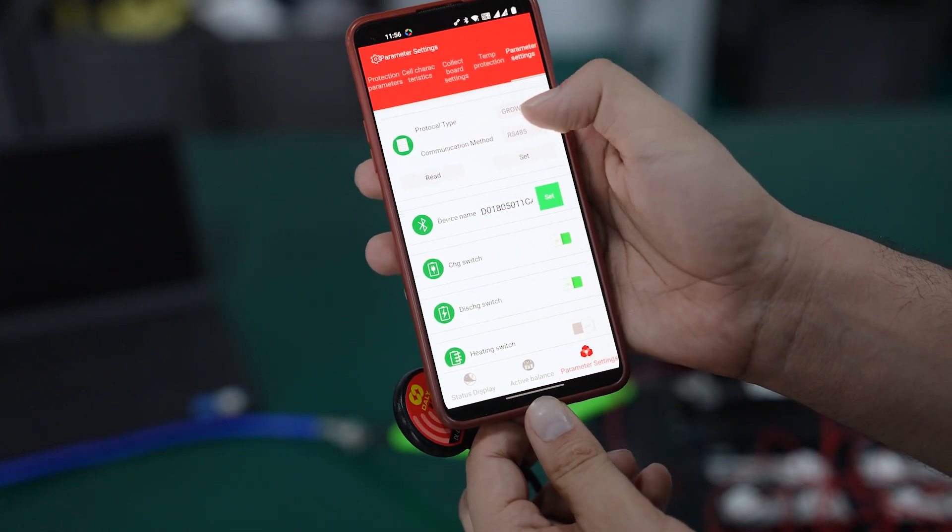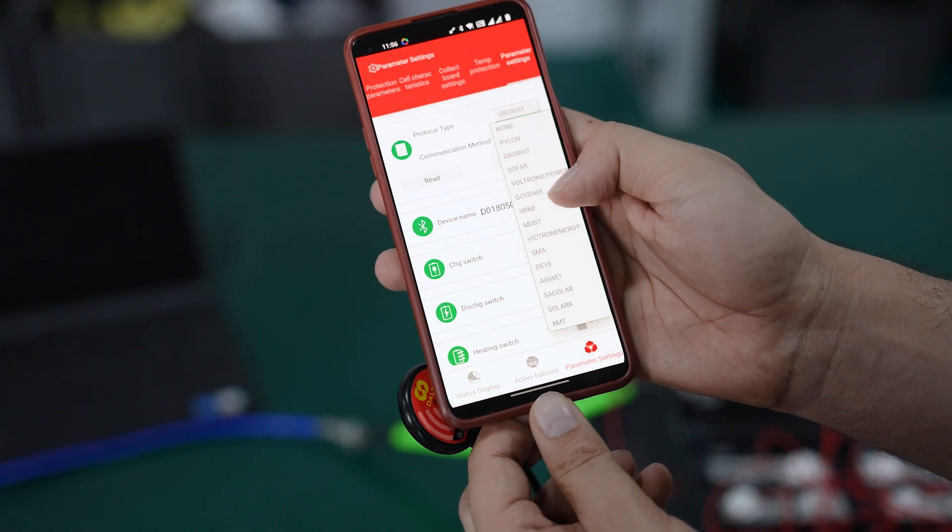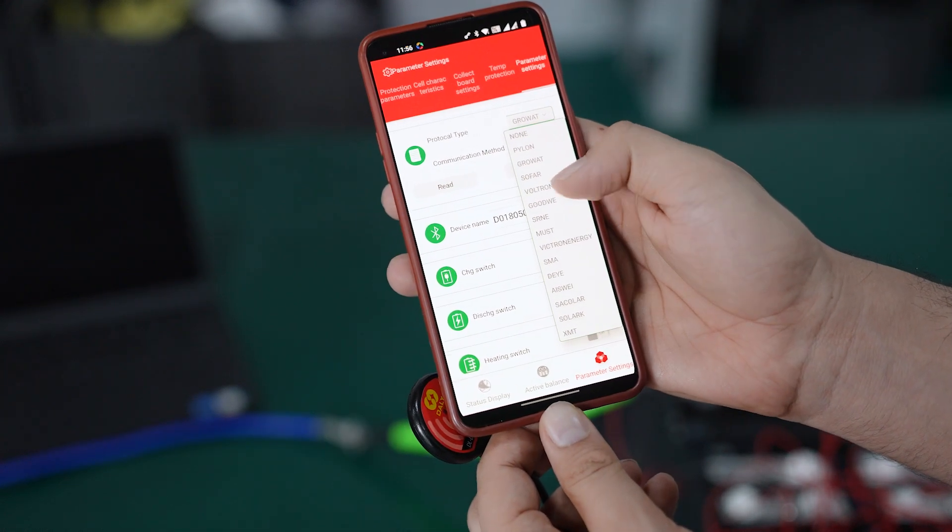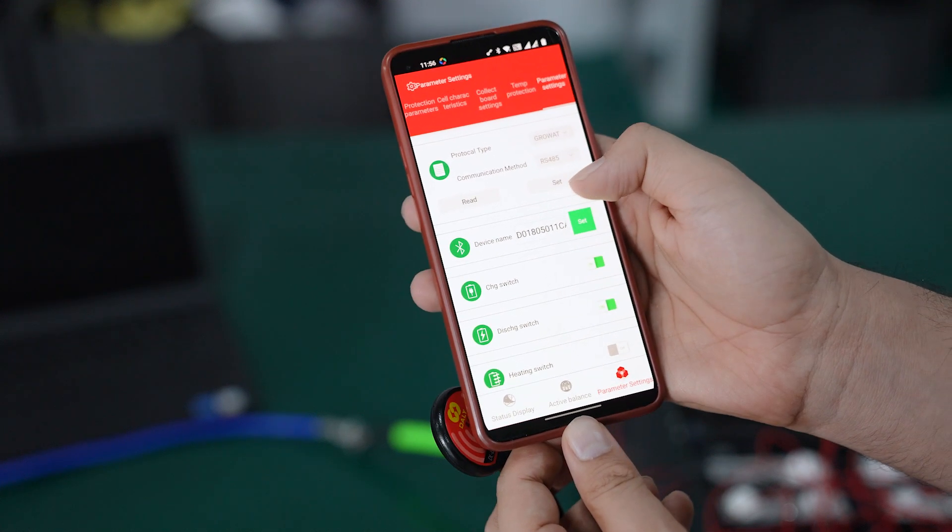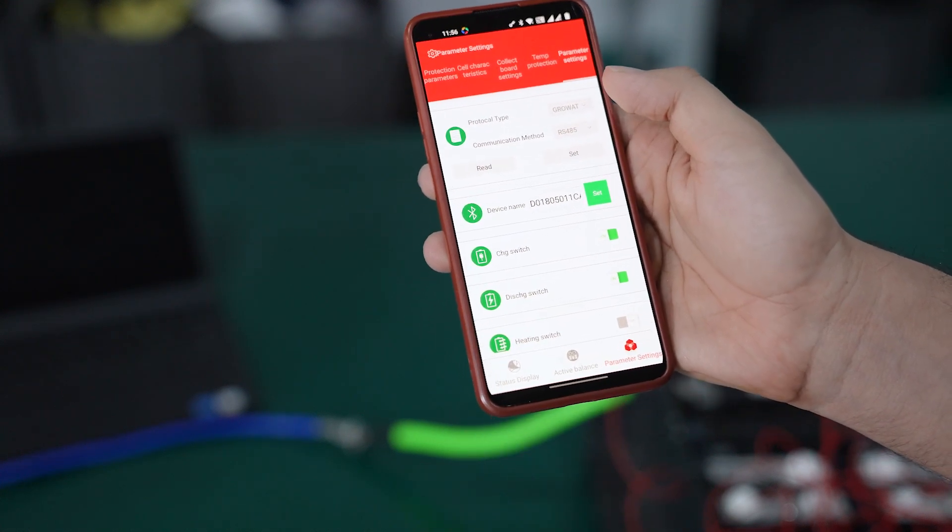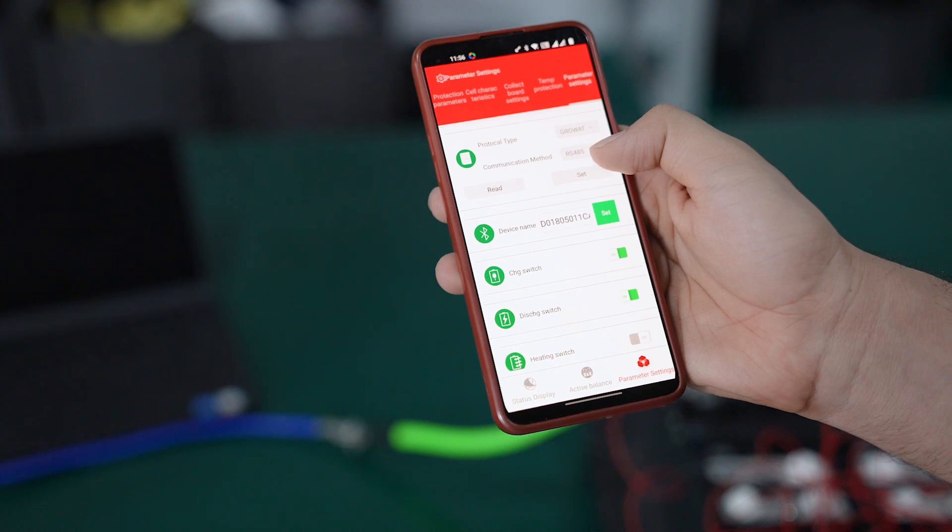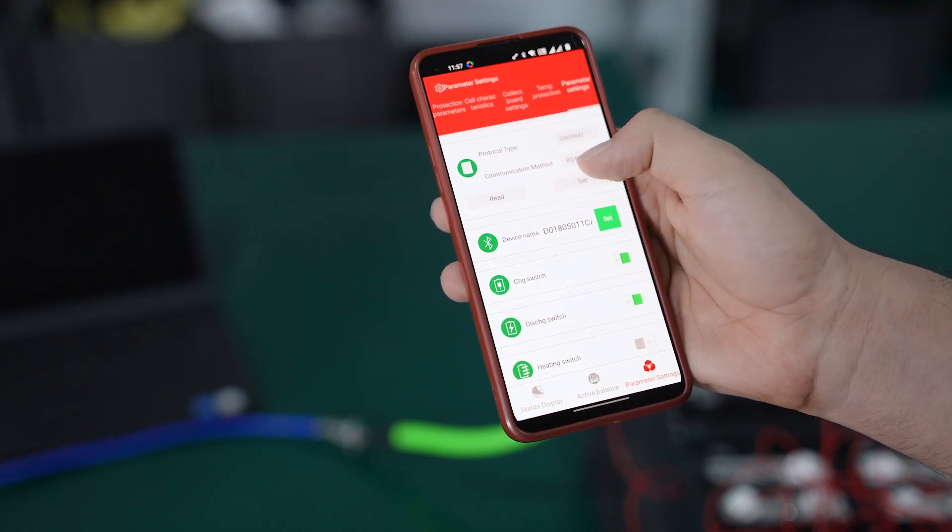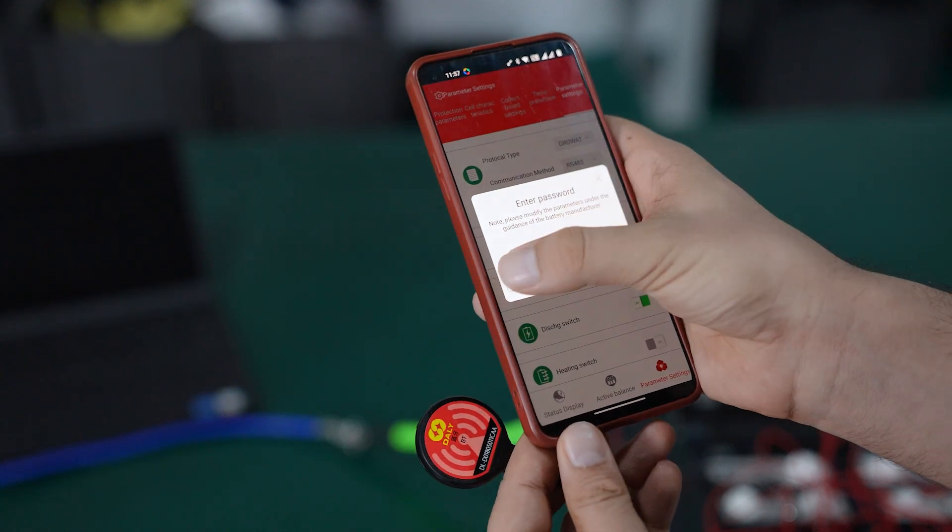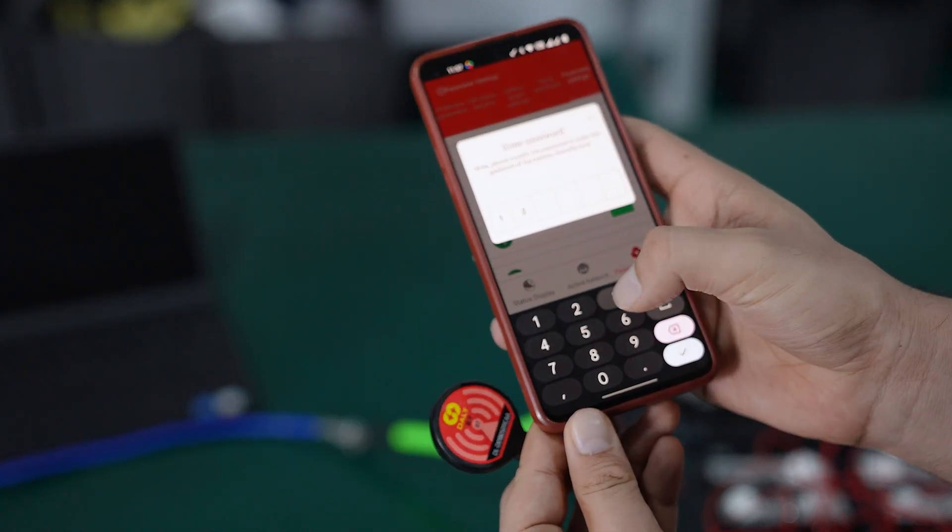There's a protocol type where you can select any inverter brand. You can see there are a lot of inverter brands like Victron, Goodwe, and you can select Growatt here. Whatever communication method you are using—today we are using RS485—select RS485 and set. Enter the password: 1-2-3-4-5-6. It's successfully set.